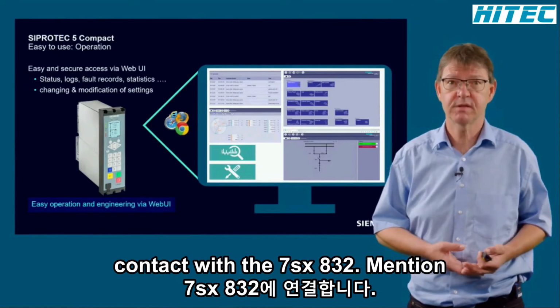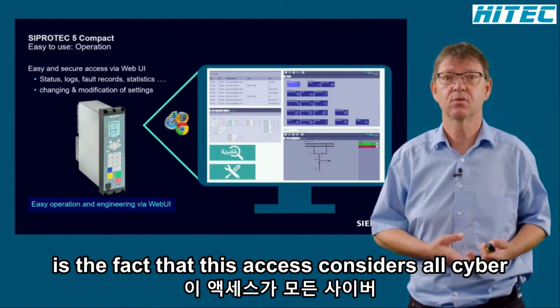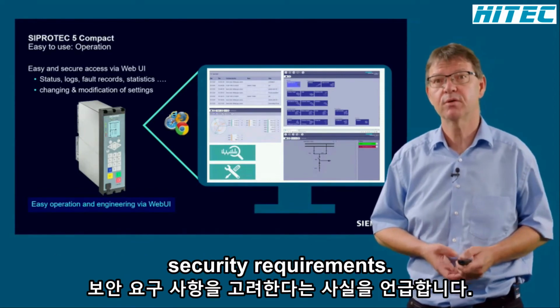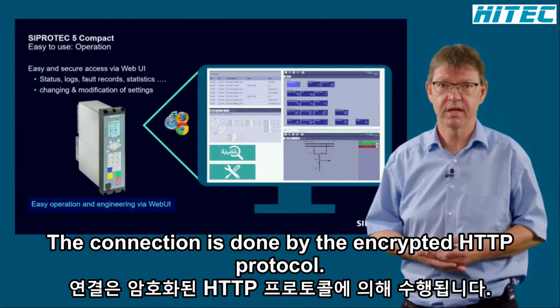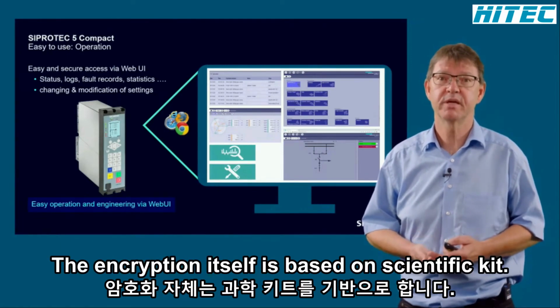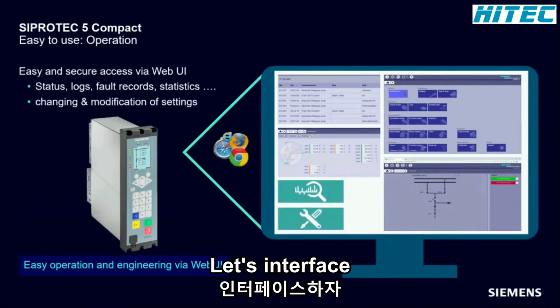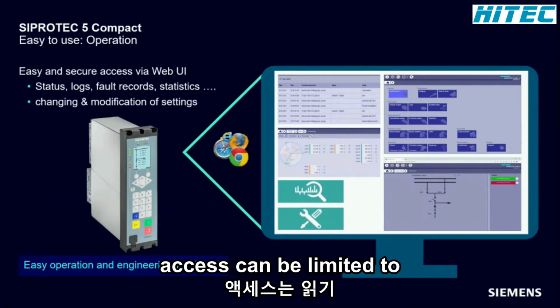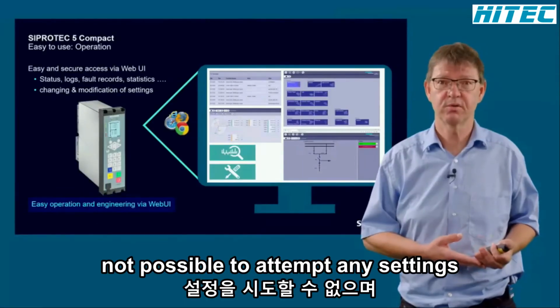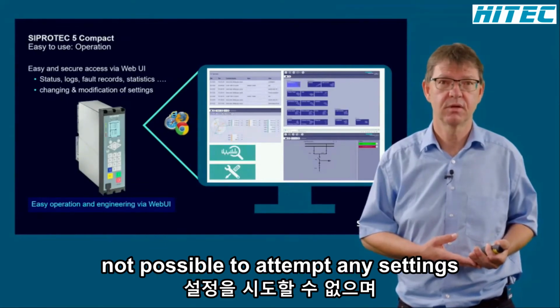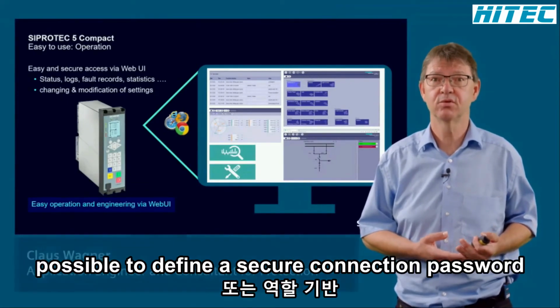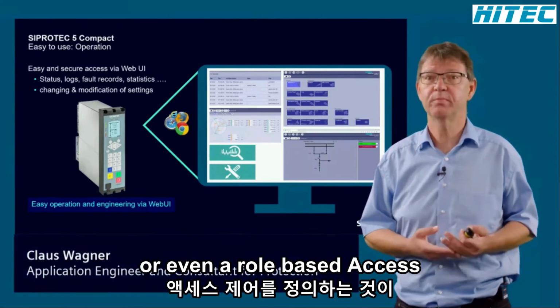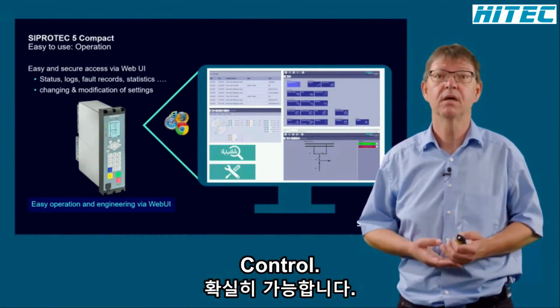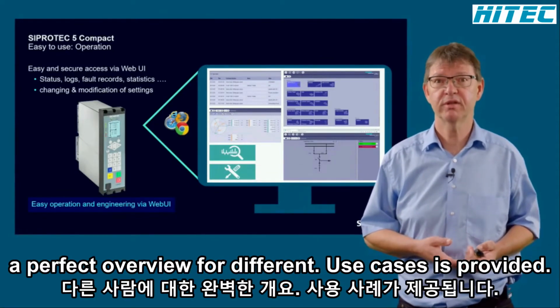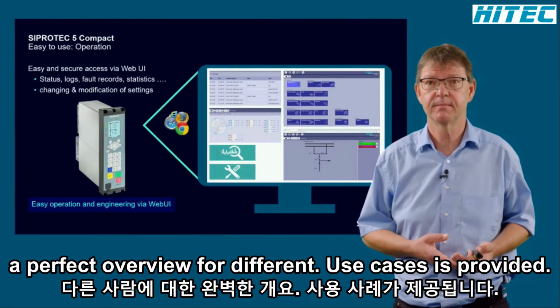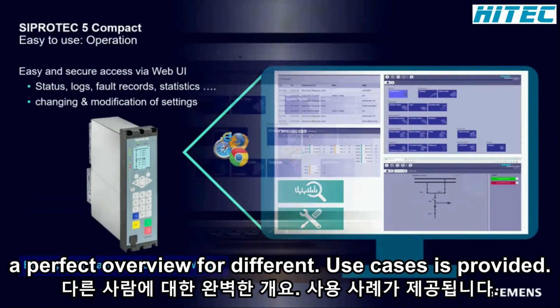Very important to mention is the fact that this access considers all cybersecurity requirements. The connection is done via the encrypted HTTPS protocol. The encryption itself is based on certificates. The Ethernet interface access can be limited to read only, so that it's not possible to adapt any settings. And it's for sure possible to define a secure connection password or even a role-based access control. Via a state-of-the-art dashboard, a perfect overview for different use cases is provided. So let's have a closer look at that.